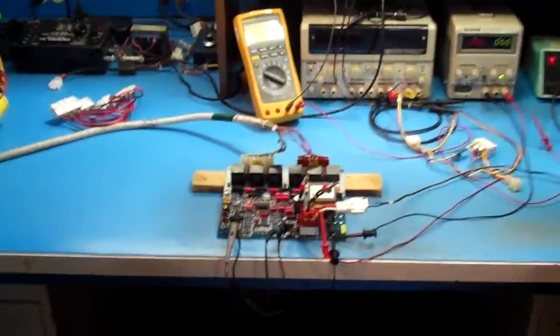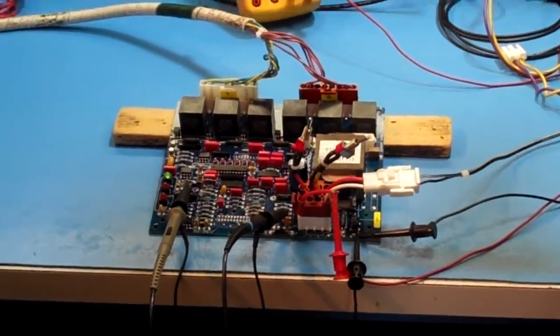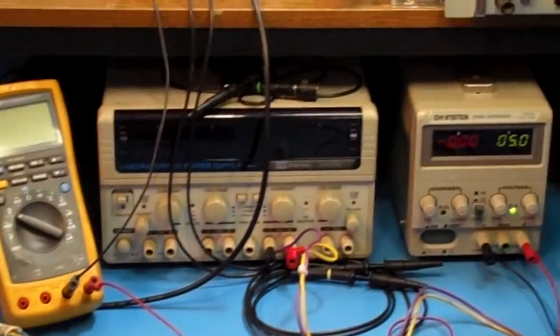This is our second video, Thursday, June 7th. This is the 6100 board, and we were able to pull up board serial number 97704. So we've gone through the settings. It's properly set up as an AC controller.